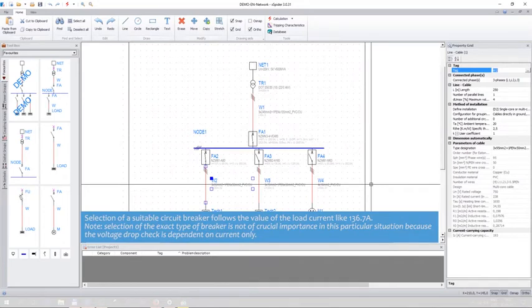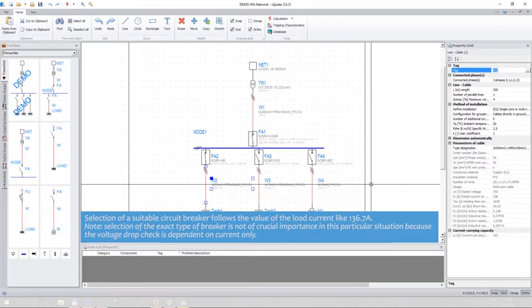Selection of a suitable circuit breaker follows the value of the load current, such as 136.7 amps. Please note, selection of the exact type of breaker is not of crucial importance in this particular situation, because the voltage drop check is dependent on current only.